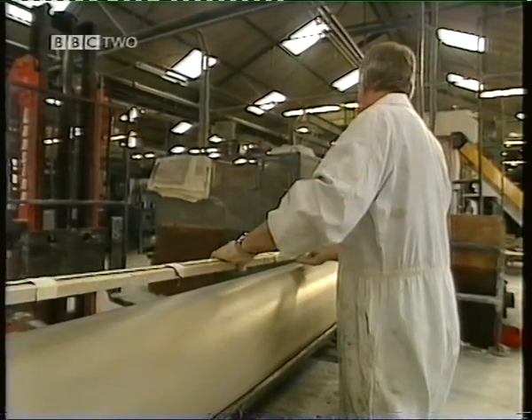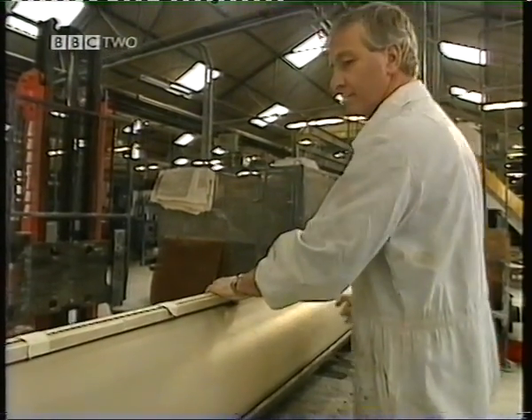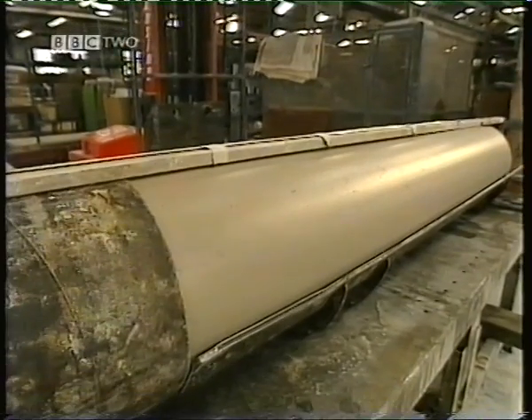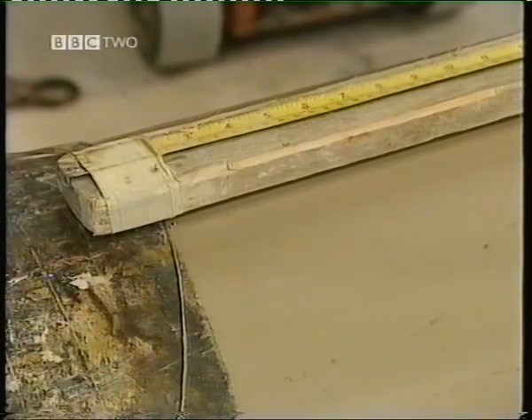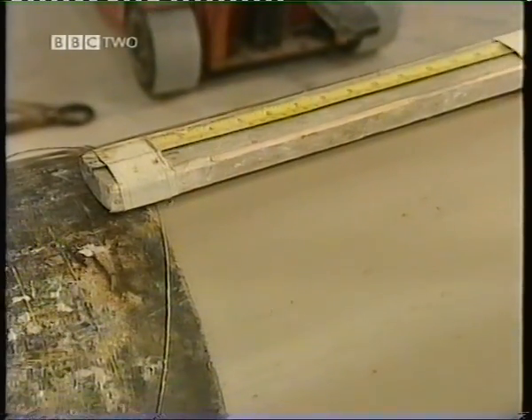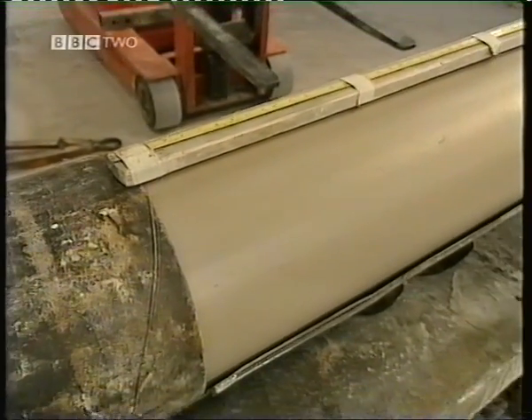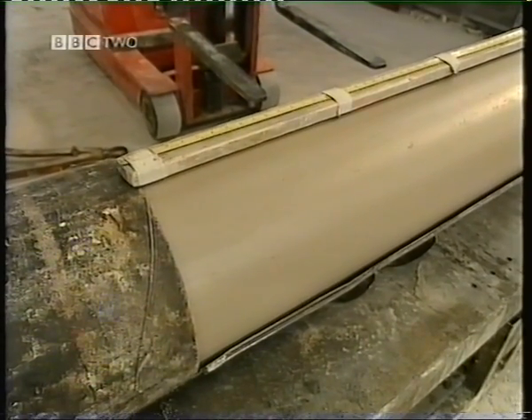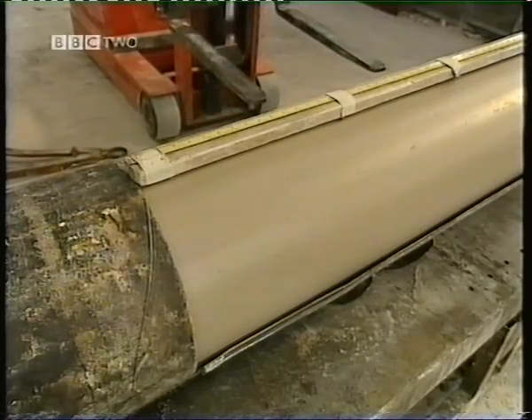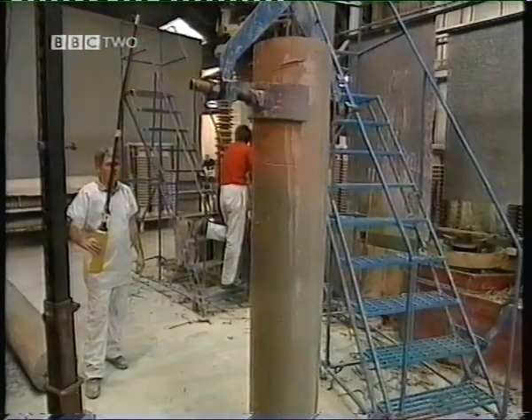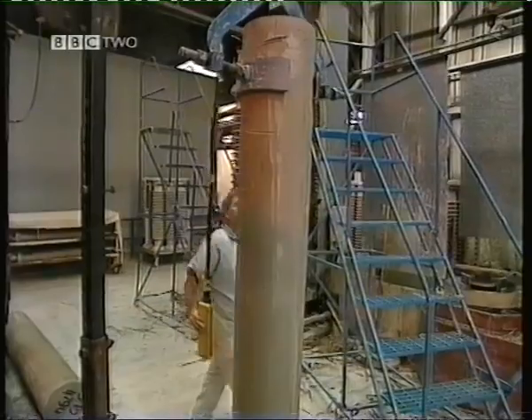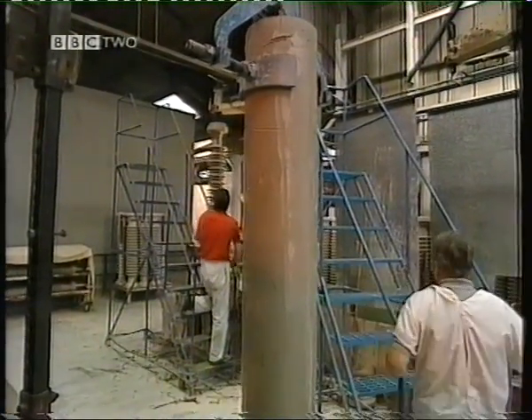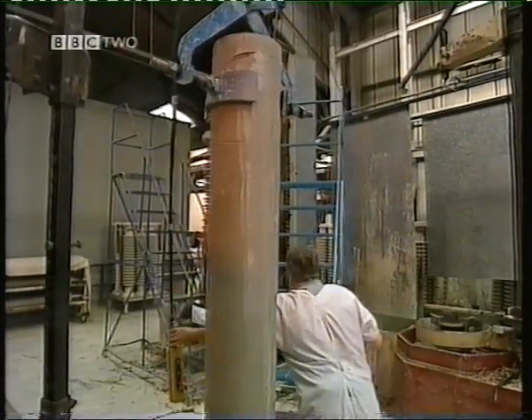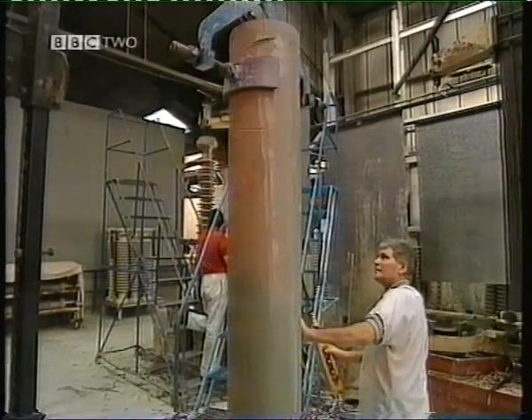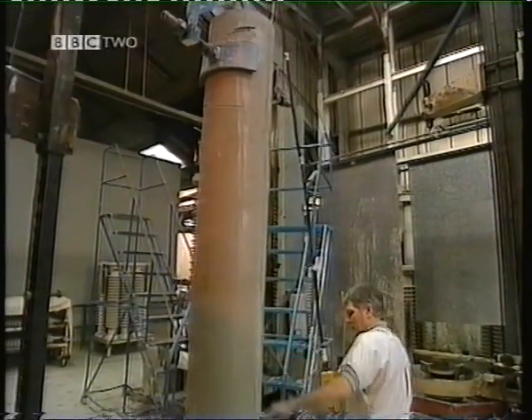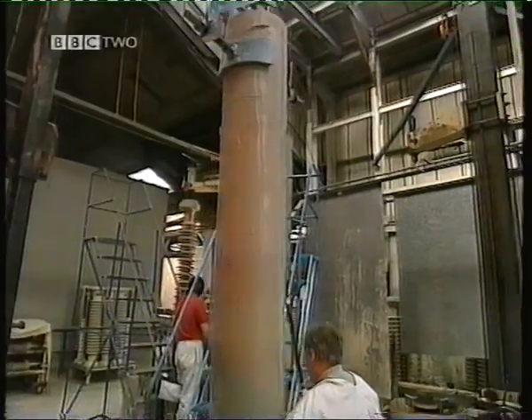These clay dumps, as they're called, are then dried until they have sufficient rigidity for the next operation. Although they may look like cylinders of modelling clay, they're in fact now dry enough to be machined. Smaller insulators are mounted on horizontal lathes, but the large post insulators for supporting lines on ground-based equipment are held vertically.